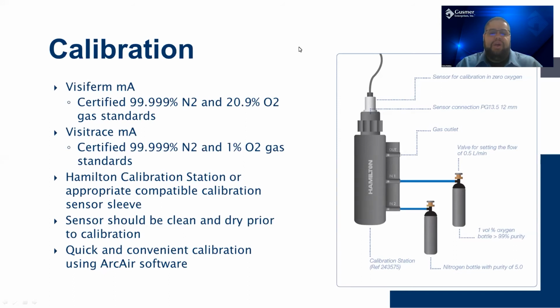There's 2 different ways you can calibrate the sensors. Hamilton has what's called a calibration station, where you can connect your certified gases to this device, and then you can screw in your sensor at the top, and then valve open your gases appropriately, and use the ArcAir software to calibrate. The other way you can calibrate is there's what's called a calibration sleeve, which Hamilton also offers, but you can just connect the tubing on the sleeve to your gas, and then slip the sensor right into the sleeve.